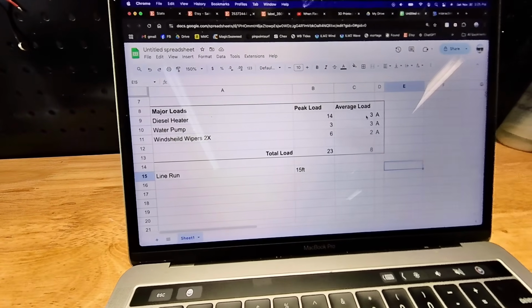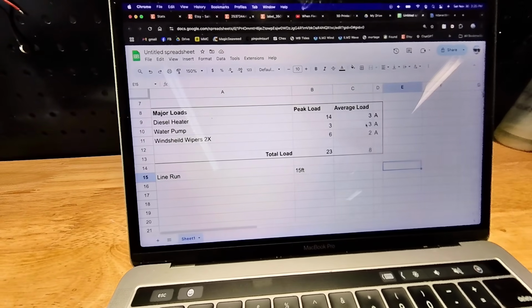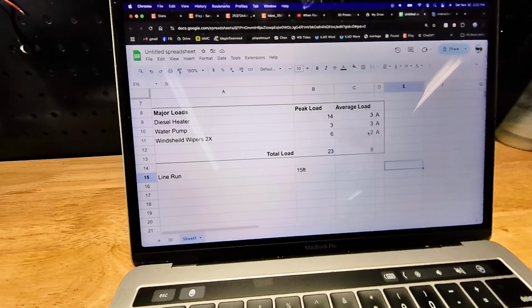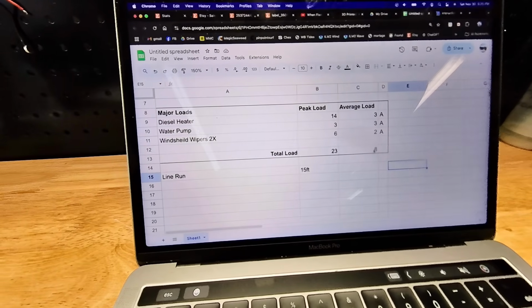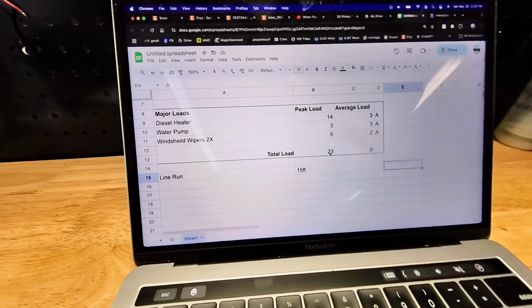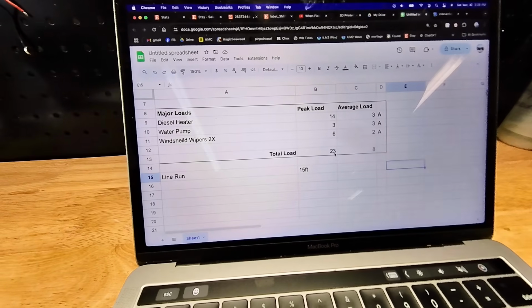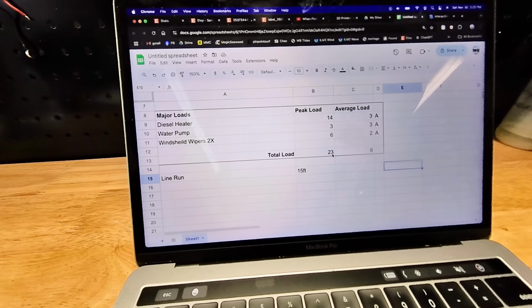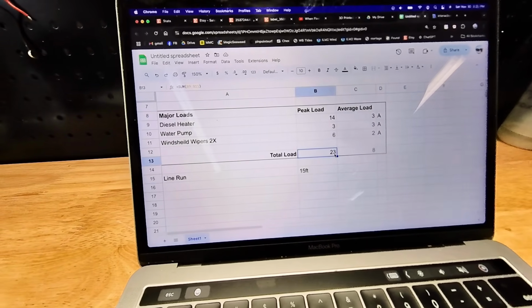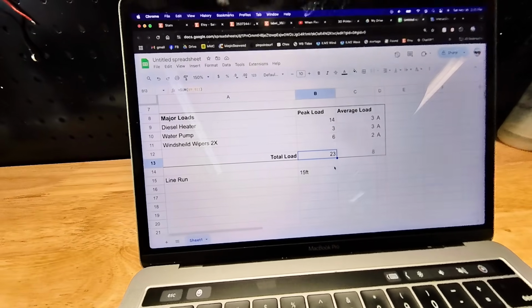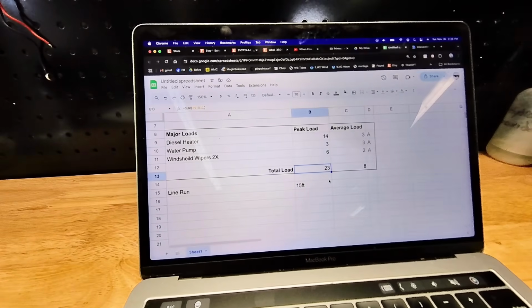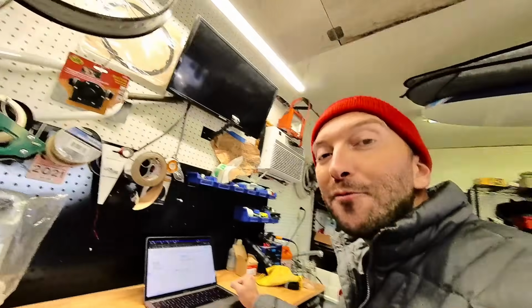Realistically, when the diesel heater is already warmed up, and with a more typical current draw for the windshield wipers, we'd be pulling closer to 8 amps. But I want to try to size this system to handle anything we can throw at it, so let's go for the peak load, which is 23 amps. That'll give us some headroom too, so when we add accessories in the future, we'll have a little bit of headroom to grow into.